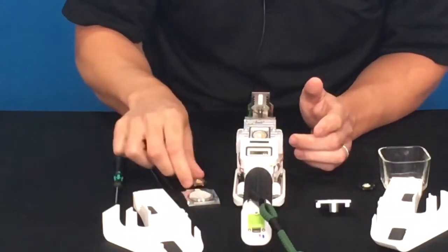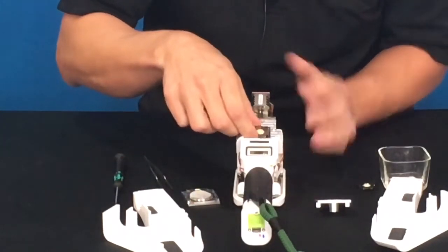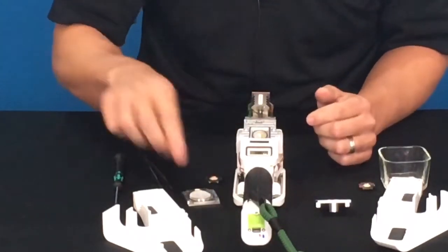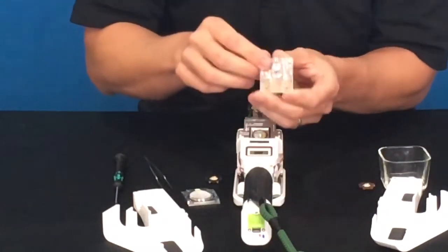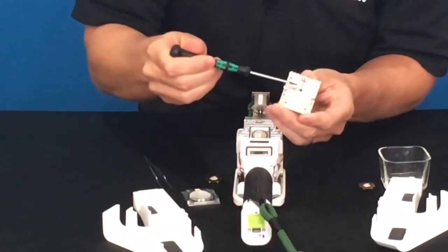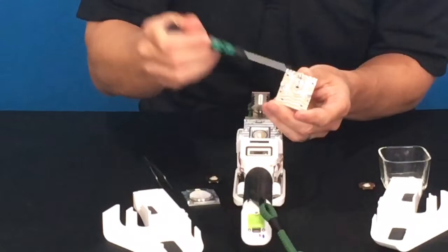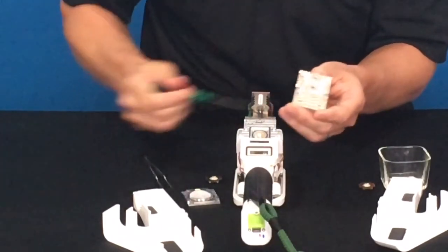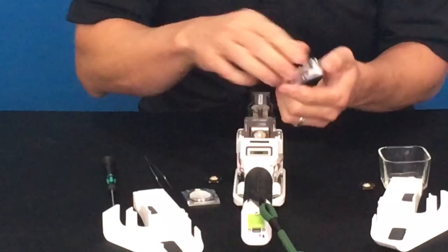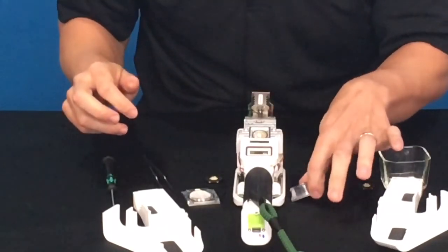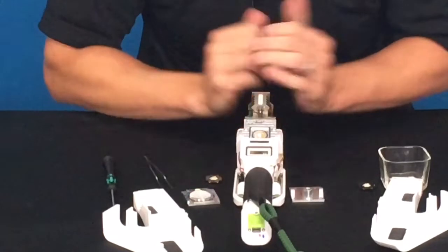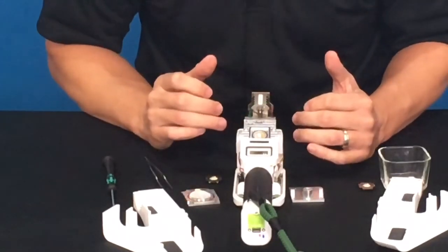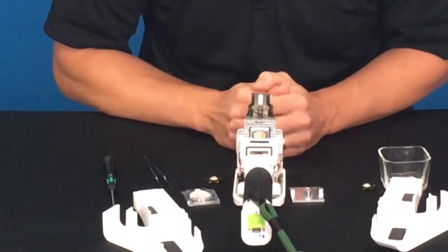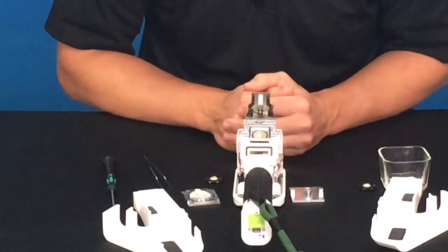And then you can just put your pump back in place and put it all back together, which we'll show here in a minute. And then the manual will have more information on this. You can thread a 10-32 fitting to get to a scrub tube in here and run dry air through your system. There is an alternative method to check the zero of your RH sensors that does not require all of this disassembly, but it does require either an external pump or a tank with pressure to flow the air across the sensors. And more information on that can be found in the manual or on our website.